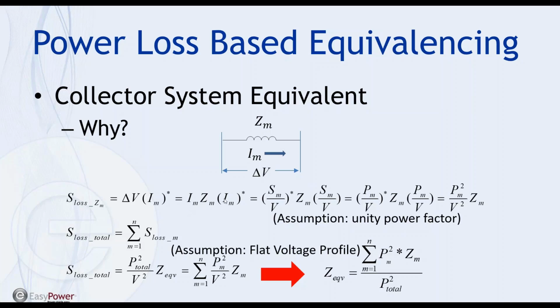And we know that Im can be written as the conjugate of apparent power, Sm, divided by the voltage, V. If we make the simple assumption here that the power flowing through the circuit has a unity power factor, then we can get rid of the conjugate sign by replacing Sm with Pm. Now Pm becomes a real number, and V can always be represented as 1 with angle 0. So you don't have any imaginary part at all. So you get rid of the conjugate sign, and the total loss on this circuit would be the active power flowing through this circuit squared divided by the voltage squared, times the impedance. So the total loss from your one line would be the sum of all the circuit losses.